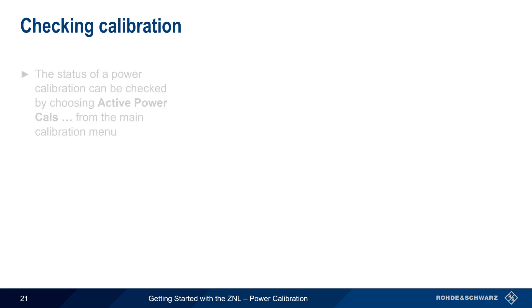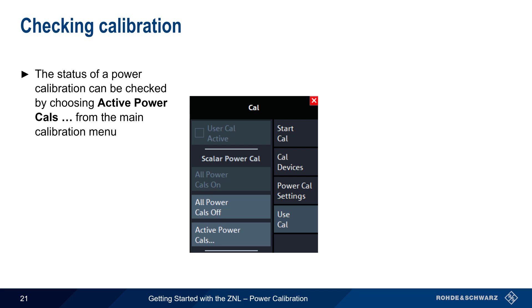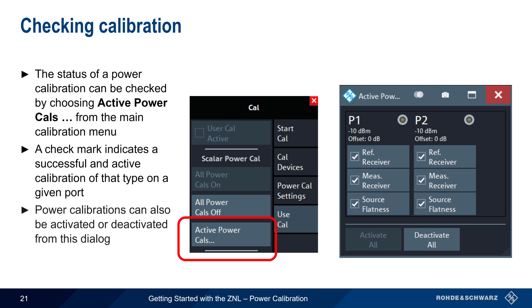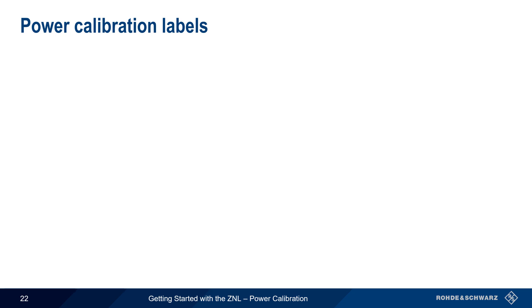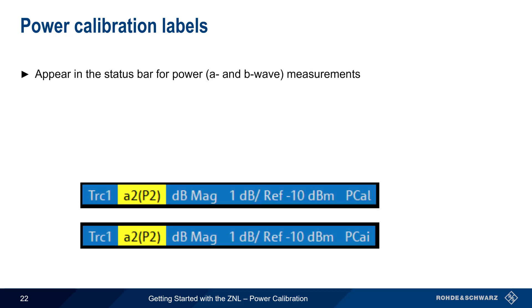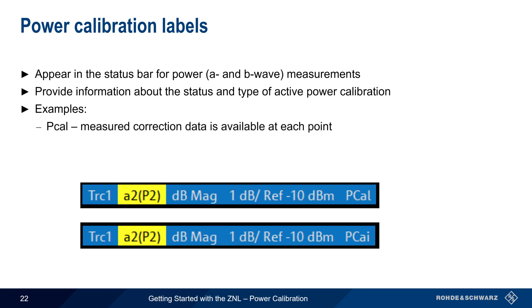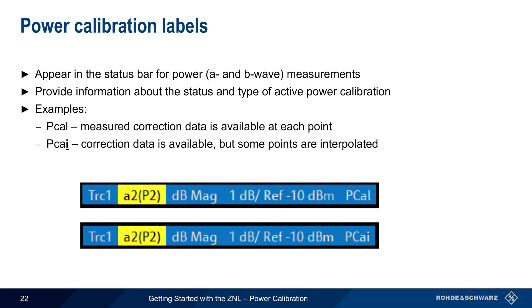Once power calibration is complete, the status of that calibration can be checked by going to the calibration menu and selecting Active Power Cals. A check mark indicates a successful and active calibration of that type on a given port. If needed, an active power calibration can also be deactivated using this dialog. Power calibration labels appear in the status bar for any power or wave measurements, providing information about the type and status of any current and active power calibrations. For example, the label PCAL will appear whenever measured correction data is present at each sweep point. If interpolation of the data is being performed, then PCAI will appear as a label. Please see the ZNL documentation for a complete list of label types and meanings.